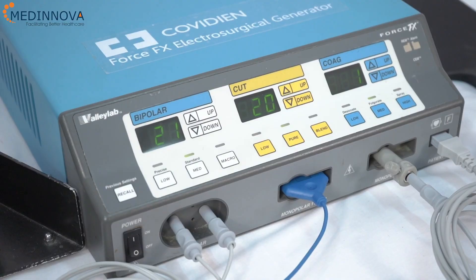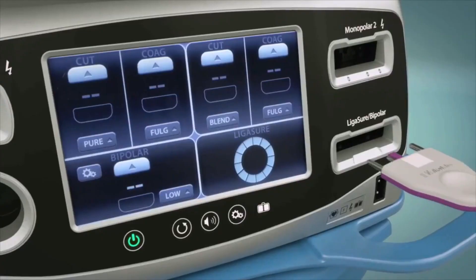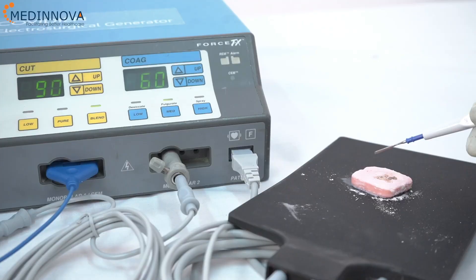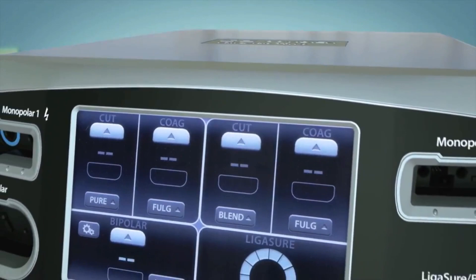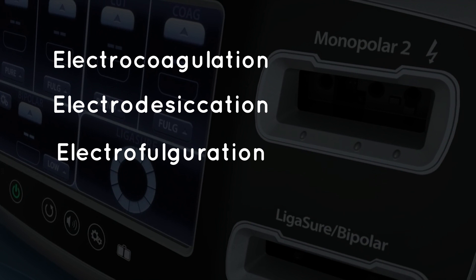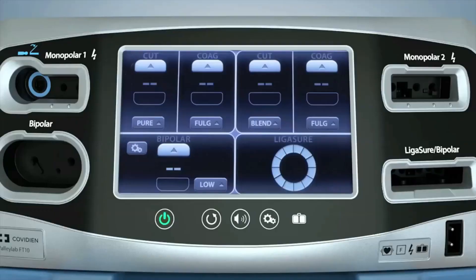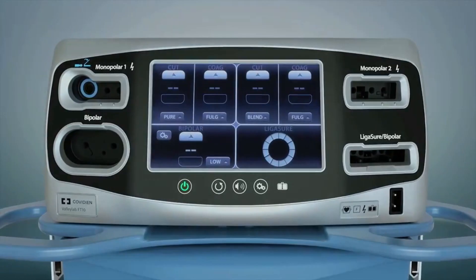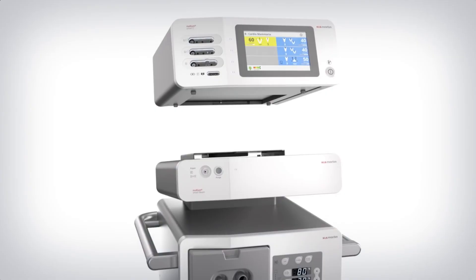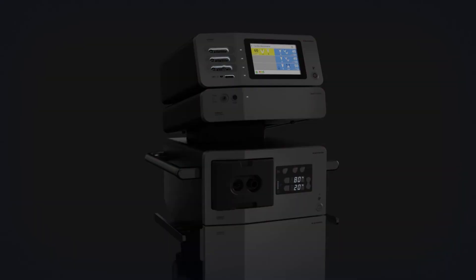Let's look into the types of electrosurgery units. The two types most commonly used are high-frequency electrosurgery and electrocautery. High-frequency electrosurgery refers to four different methods: electrocoagulation, electrodesiccation, electrofulguration, and electrosection. These methods involve high-frequency alternating current, which is converted to heat by resistance as it passes through the tissue. The result of heat buildup within the tissue is thermal tissue damage. These modalities are commonly used for hemostasis, debulking procedures such as rhinophyma excision, and treatment of benign and malignant skin conditions ranging from acrochordons to basal cell carcinoma.